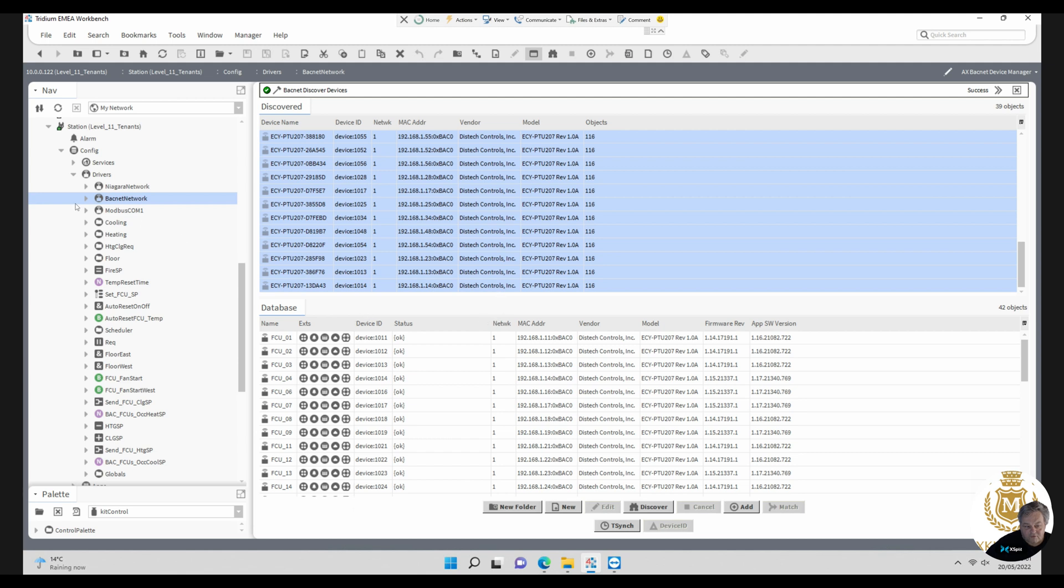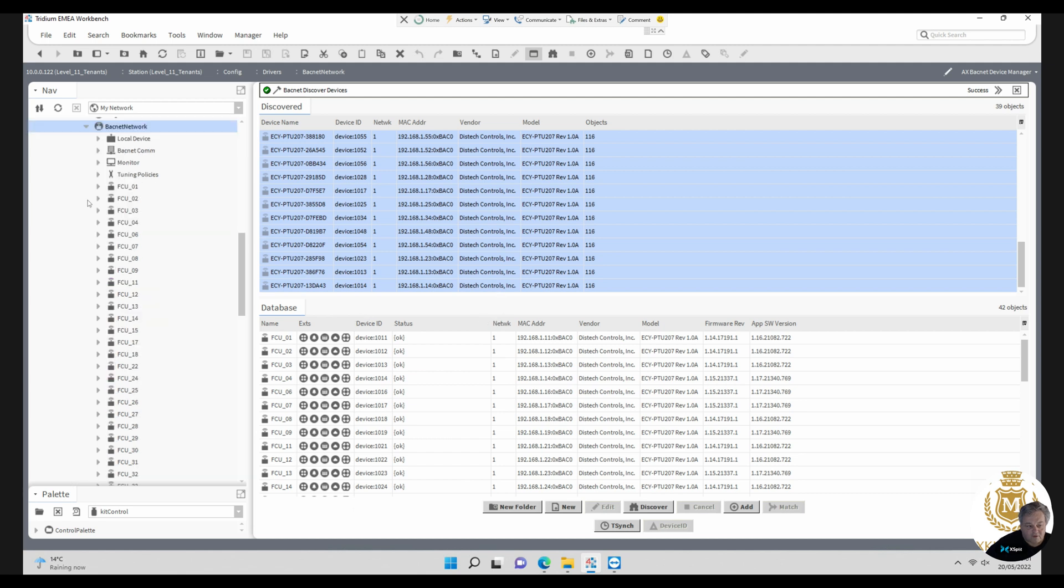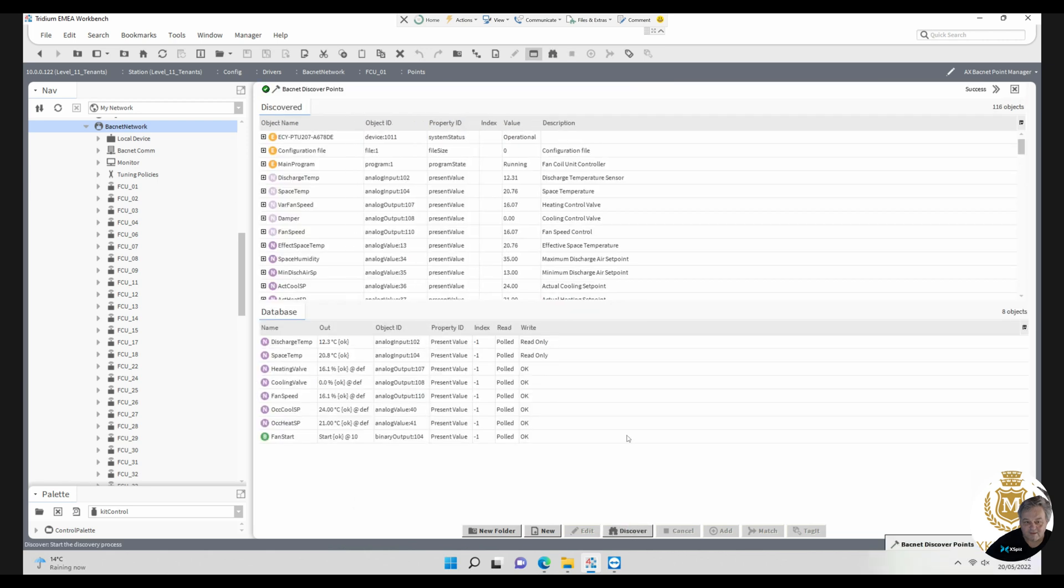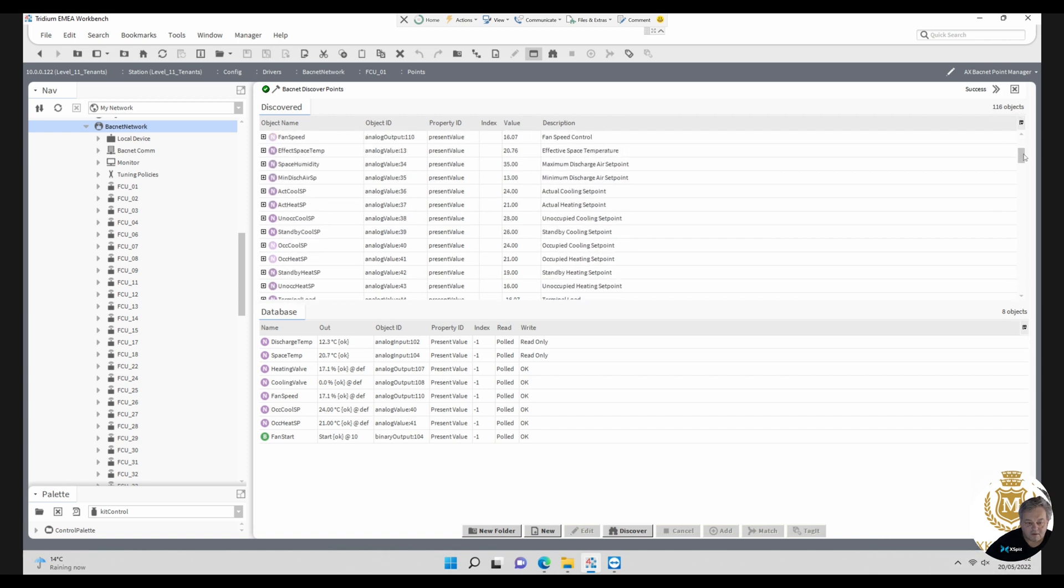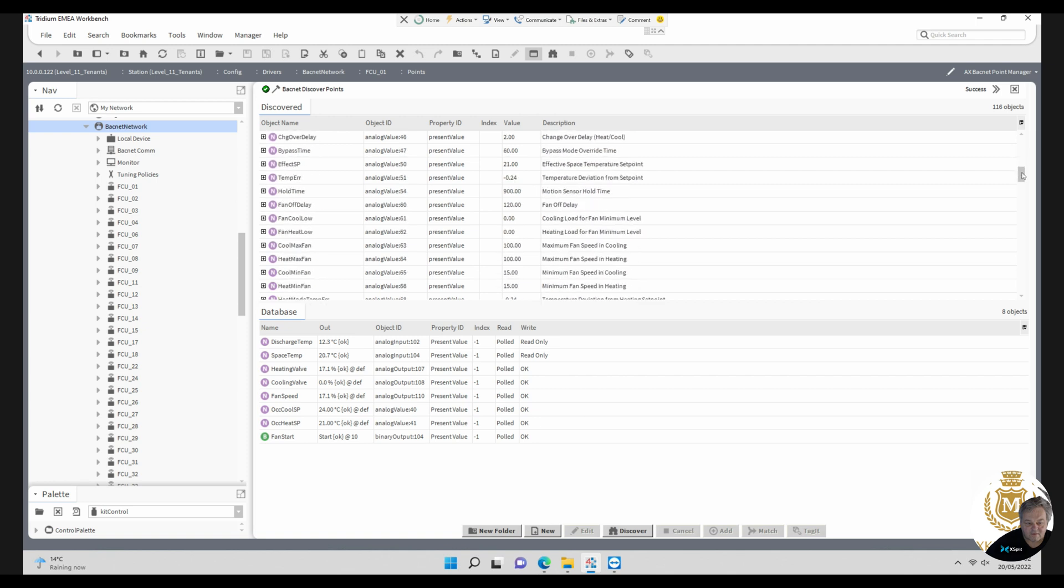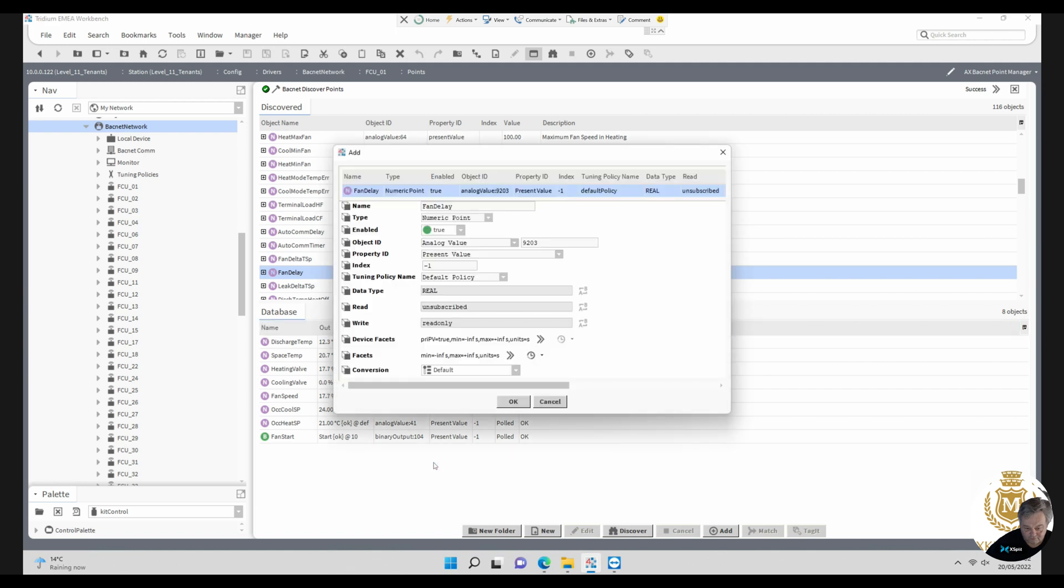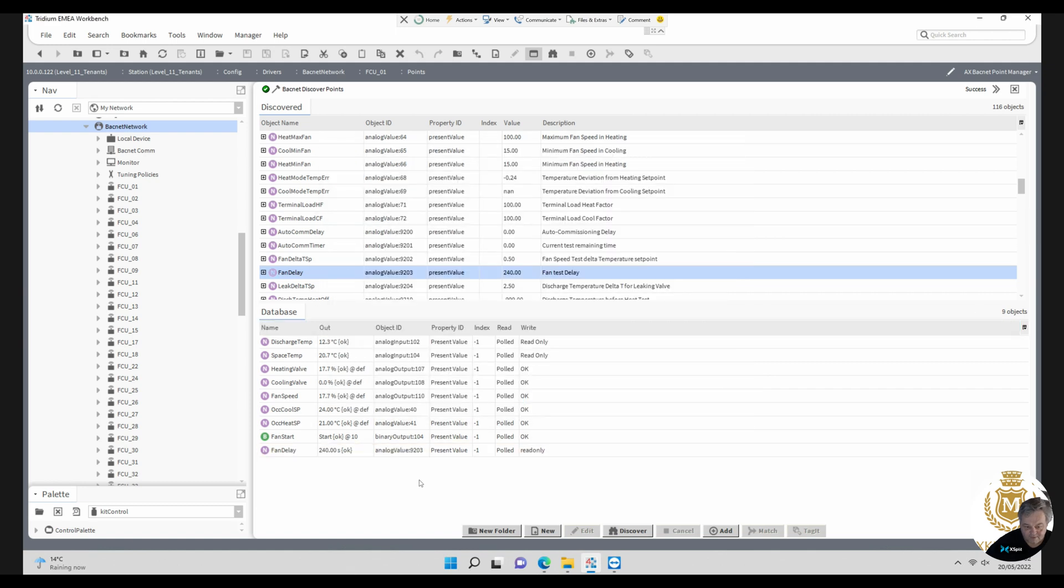Once you've got a fan coil, you can go into the points of a fan coil and these are the points here. There's a lot more points than just these, but what you can then do is discover. This is discovering the point, so these are all the points. There's 116 objects and you can see all these points here. It's as simple as clicking on the point and dragging it down. That's it, that point is there. I'll delete that point out.